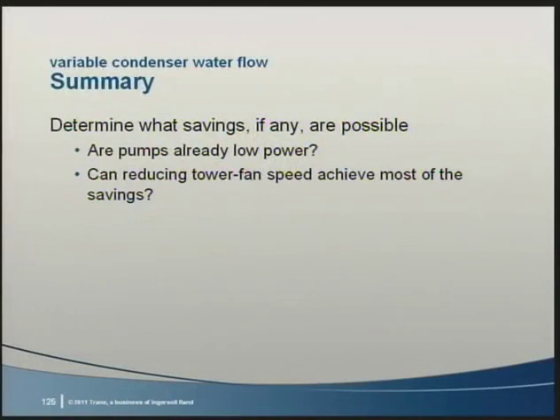First, you need to determine whether or not reducing condenser water flow rates should even be considered. If you're already minimizing the condenser water pump kW, for example, by reducing its design flow rate to 1.5 or 2 GPM per ton, it may not even make sense to take the time to look further. Also, reducing just the tower fan speed may give you most of the energy savings, and it's simpler.